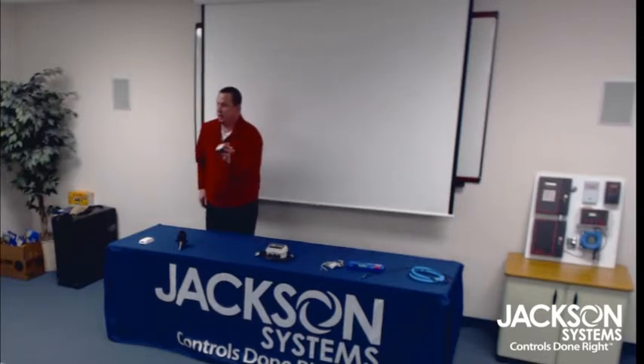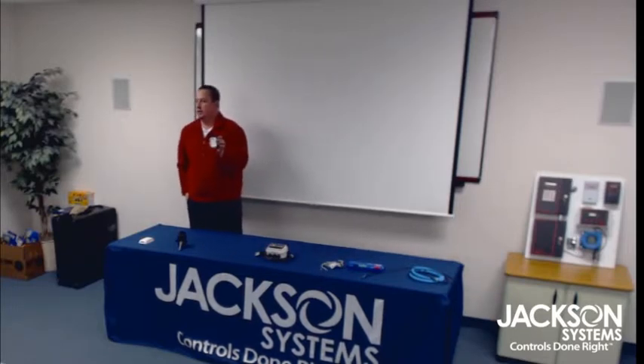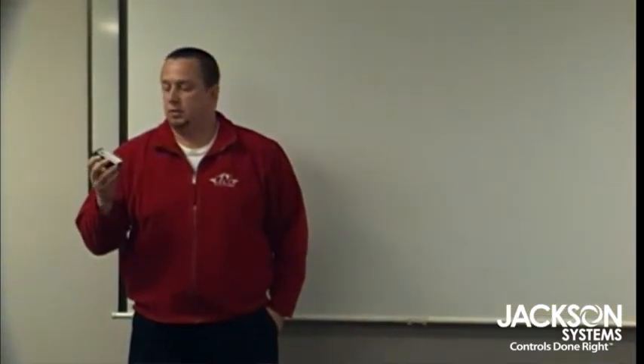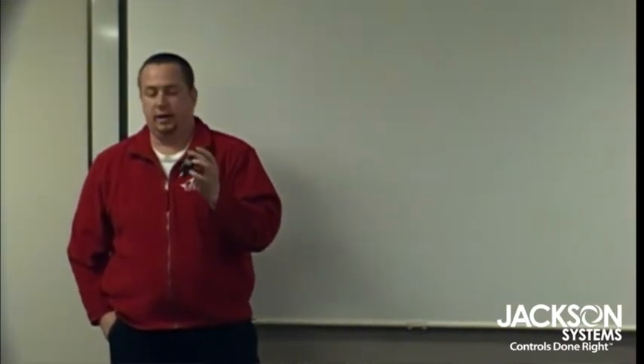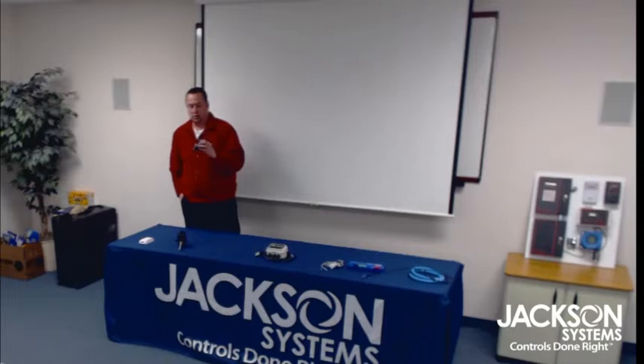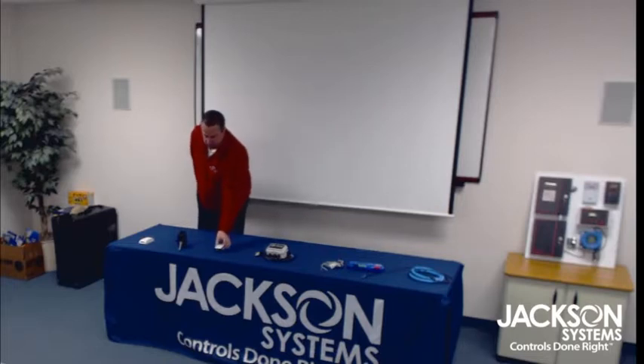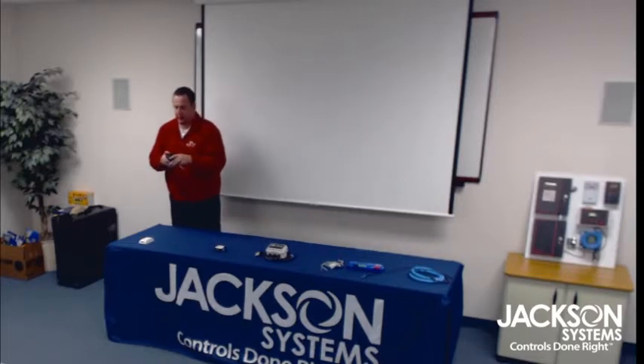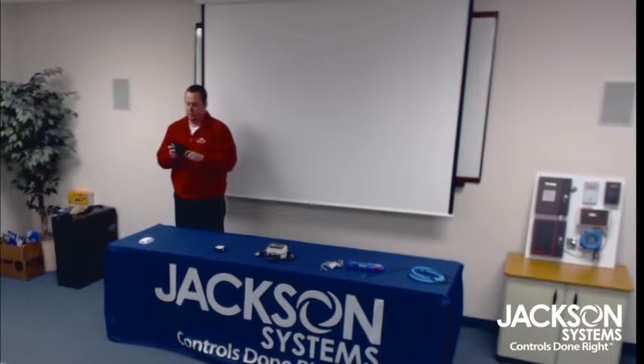So as you mentioned, we have inches of water column, so dry side, and we can go down to 0.1 inches water column, all the way up to, I believe, 20 inches of water column. So this is our new mini low pressure, or MLP. It's a lot smaller footprint, smaller design enclosure. It also has the auto zero function and the span function on the right side of the push button.